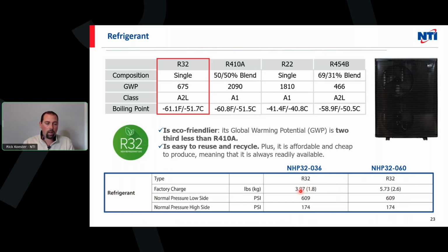So I do make a point that we are under 4 pounds on a 3-ton system and just under 6 pounds on the 5-ton. So potentially, if you had an application in a garage or an enclosed space, as long as we had the air volume there, as long as you're under that 4 pounds, and that's what they're looking for, we don't need ventilation and leak detection. So I like to bring that up.